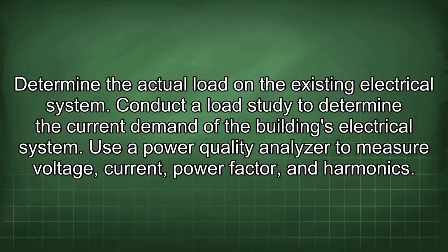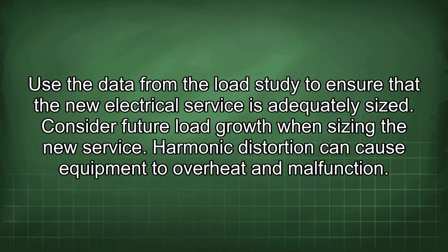Determine the actual load in the existing electrical system. Conduct a load study to determine the current demand of the building's electrical system. Use a power quality analyzer to measure voltage, current, power factor, and harmonics. Use the data from the load study to ensure that the new electrical service is adequately sized. Consider future load growth when sizing the new service.